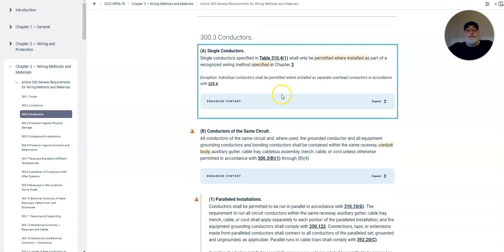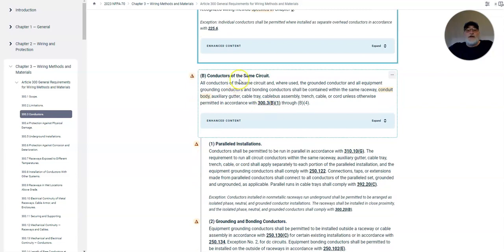All conductors. Let's go to B. Now, that was A. Let's go to 300.3(B). All conductors of the same circuit and, where used, the grounded conductor and all equipment grounding and bonding conductors shall be contained within the same raceway, conduit body, auxiliary gutter, cable tray, cablebus assembly, trench, cable, or cord unless otherwise permitted in 300.3(B)(1) through (B)(4). And that's going to be what these are down here. Now, what does that mean? Okay, what is that talking about? That's talking about if you have, for example, a three-phase system, okay, and you're bringing your incoming power coming from your transformer, coming from another panel, your hots, A, B, and C phase, your neutral, and your ground have all got to be in the same conduit.